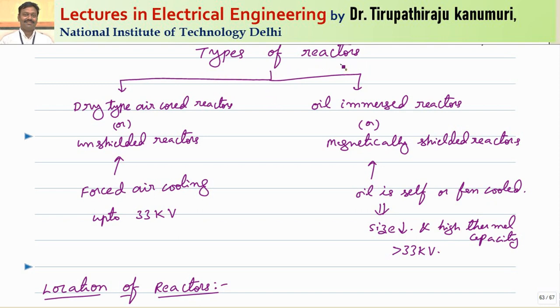Now let us see the types of reactors. Reactors are either air-wound, or if a core is used, holes are incorporated to reduce the effect of saturation. Depending on construction type, the first category is dry type air-cored reactors, also called unshielded reactors. In this type, the reactor is wound on a simple cement-type non-magnetic structure. The disadvantage is that only air cooling is possible and proper shielding cannot be provided for the windings.